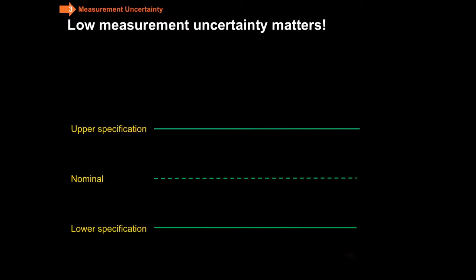So again, we'll go back to our chart, where we have a two-sided specification. And let's say we have two measurement results that are actually the same result, and they're from two different calibration labs. Now what I'm going to do is put in the ISO GUM measurement uncertainty associated with each of those measurements. So in laboratory A, in the yellow, you see a fairly small interval. In laboratory B, you see a fairly larger interval.